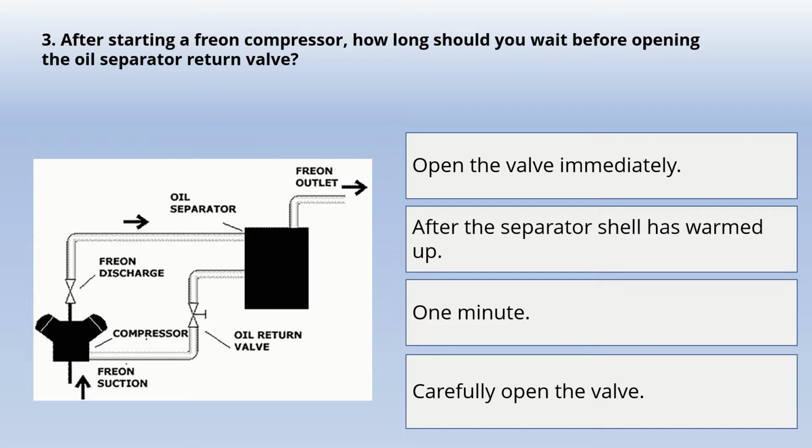Our next question is, after starting a freon compressor, how long should you wait before opening the oil separator return valve? And the options are open the valve immediately, after the separator shell has warmed up, 1 minute, carefully open the valve. And the correct option for this question is after the separator shell has warmed up.